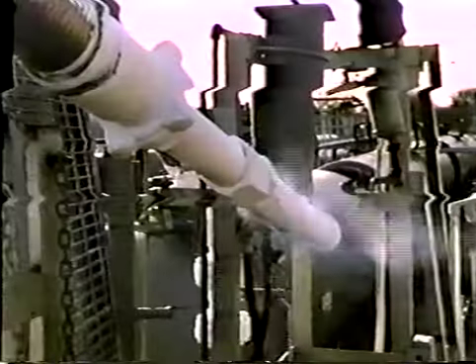Incidents involving small releases of the product occur more frequently. These can occur in refrigeration systems or during transfer operations. Pipes or valves may be damaged or fail. A tank may be overfilled. Releases can occur when refrigeration equipment or cylinders are damaged during a fire. When a discharge does occur, positive pressure SCBA for structural firefighting will provide the necessary respiratory protection. However, turnouts for structural firefighting do not provide complete protection against either the liquid or vapors of anhydrous ammonia.